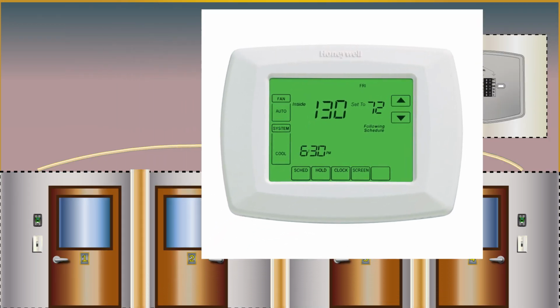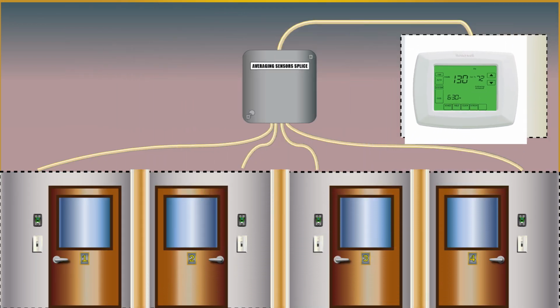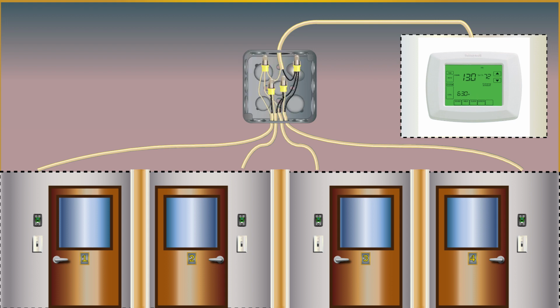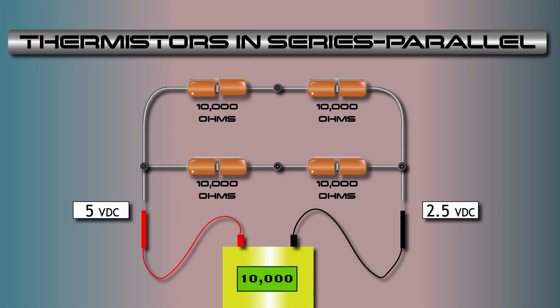For some reason, if you're getting a wacky temperature like 100 or 20 degrees, go back and check your wiring and your splices. Make sure you didn't miss something or miswire something. Going over the resistance of the thermistors in series and parallel from this video, you should be able to use your multimeter to test the wires and the splice and know what values you should have.